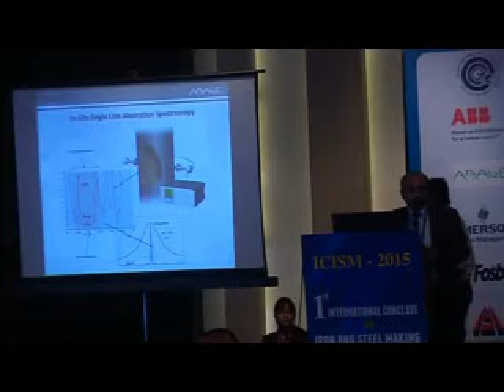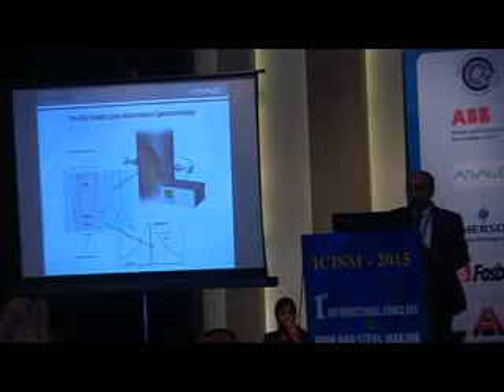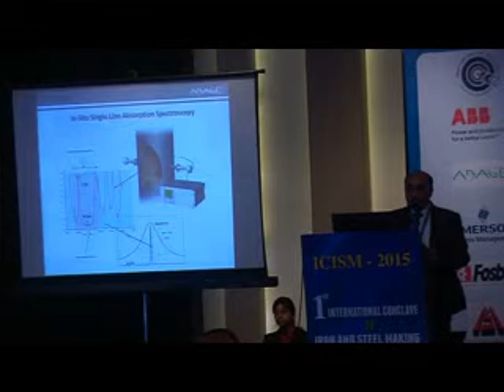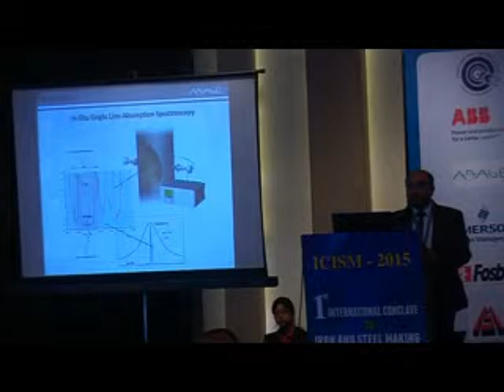A little bit about the technology - it's based on laser spectroscopy. We use the near infrared ray spectrum bandwidth. The advantage of this technology, the first and most important, as I said, is time - it's very fast, with a response time of 1 second, truly 1 second. Second, there is no cross interference with other gases. So when we know we are only measuring CO, or CO2, or oxygen, we only measure that and don't have to think about how to compensate internally with electronics and other means. That's the second most important thing.